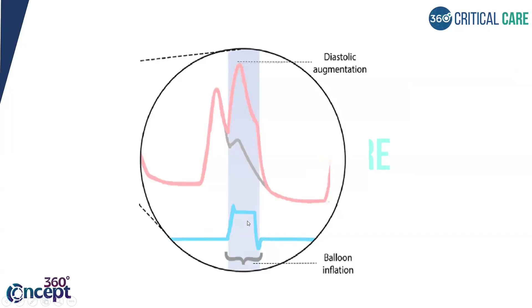So this pressure waveform is the IABP balloon pressure waveform, and this is the duration of your IABP inflation. Okay, so this is the time it gets inflated. So you get the peak of the IABP pressure. This is called overshoot. Then you have a plateau, and then it comes down, and this is the deflation of the balloon. Okay, this is a balloon waveform. So this is in particular about the balloon waveform. I told you this is your balloon overshoot. So: balloon rapid inflation, balloon overshoot, balloon plateau pressure, where there is equalization of the pressure, and rapid deflation. So this is balloon deflation.